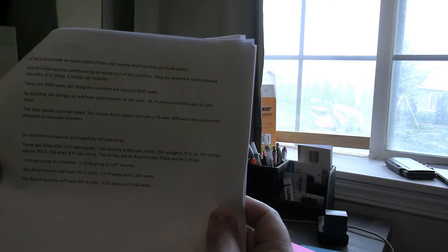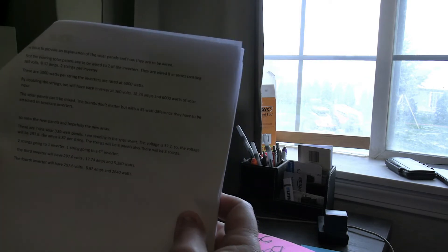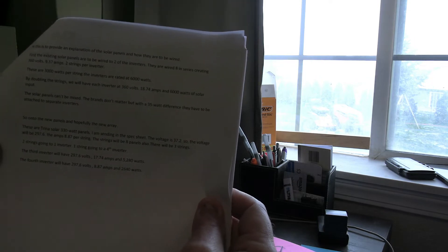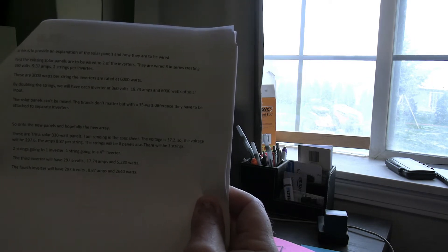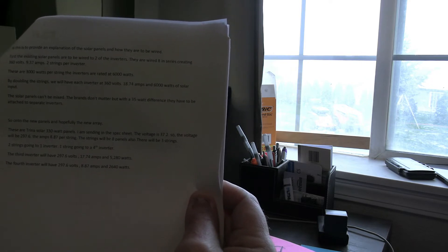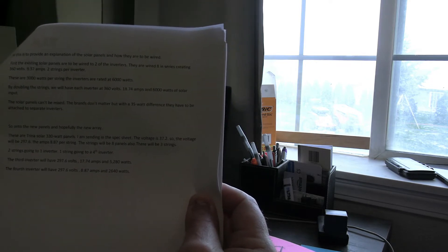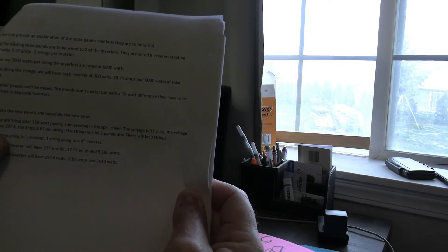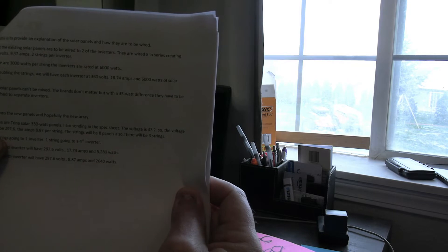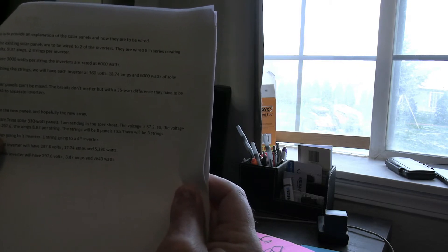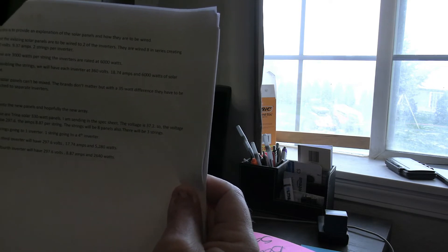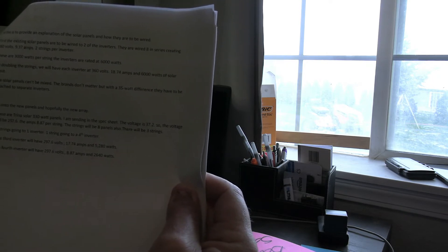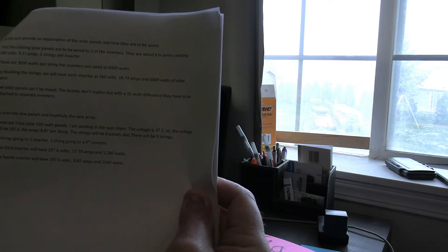This is after I was denied the first application. These are Trina Solar 330 watt panels. I am sending in the spec sheet. The voltage is 37.2 so the voltage will be 297.6. The amps 8.87 per string. The strings will be eight panels also.